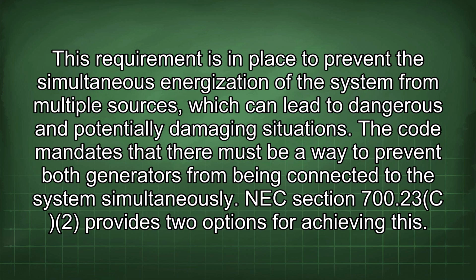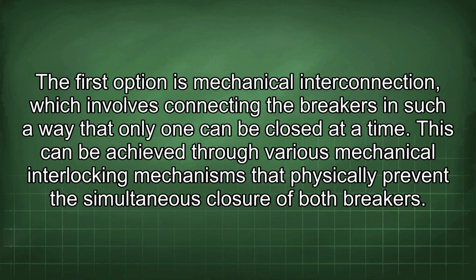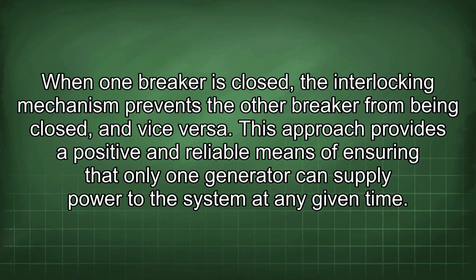NEC Section 700.23c2 provides two options for achieving this. The first option is mechanical interconnection, which involves connecting the breakers in such a way that only one can be closed at a time. This can be achieved through various mechanical interlocking mechanisms that physically prevent the simultaneous closure of both breakers. When one breaker is closed, the interlocking mechanism prevents the other breaker from being closed, and vice versa.